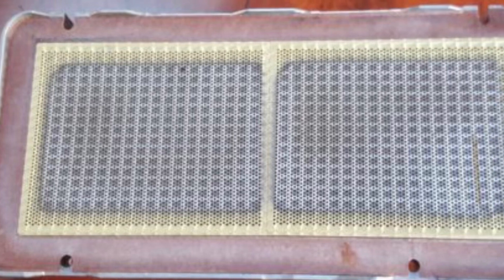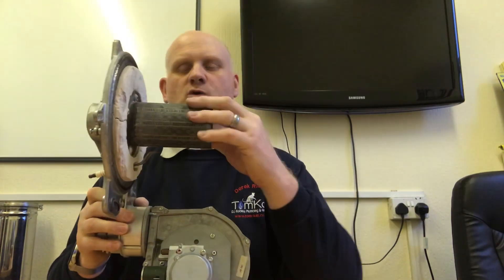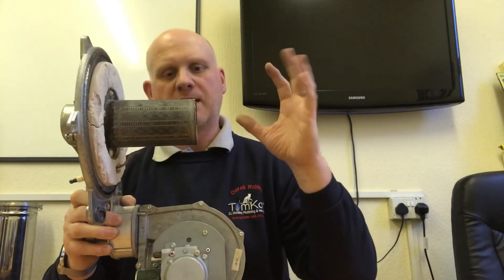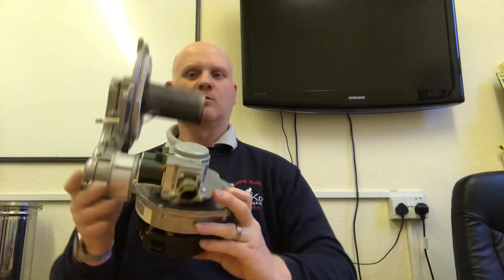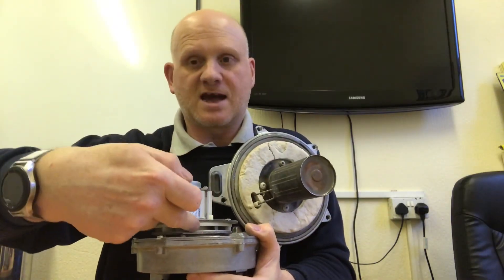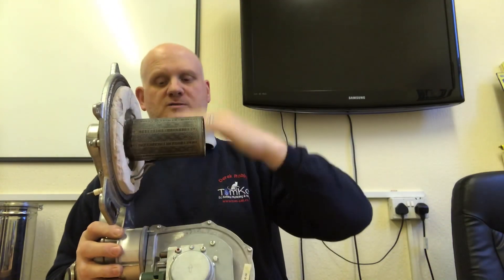Ariston Boilers was founded in 1960 in Italy, where they produced electric water heaters. The next evolution is the 360-degree burner, which was used on the condensing heat-only boiler, condensing combi, and system boiler. The gas burns 360 degrees around this cup burner. The gas comes in through the gas valve, the air mixes with the gas, goes through the blending tube mixing them together, and then burns 360 degrees.